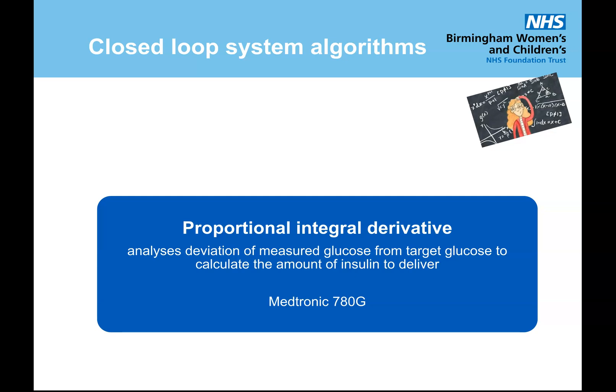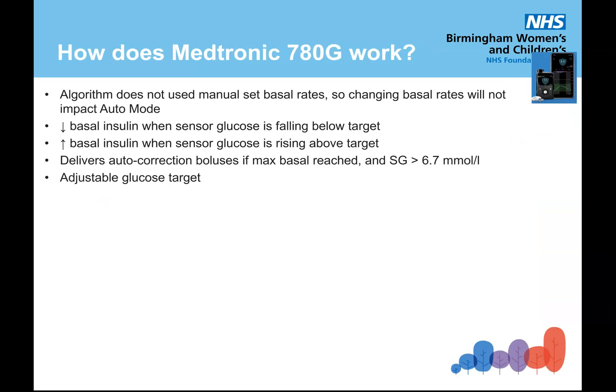It runs by a proportional integral derivative method which basically analyzes the deviation of measured glucose from a target glucose — where you want it to be — to calculate the amount of insulin to deliver. Importantly, the algorithm does not use manually set basal rates, so changing the basal rates will not impact auto mode, and it will therefore keep up to date with the person's individual needs on an ongoing basis.